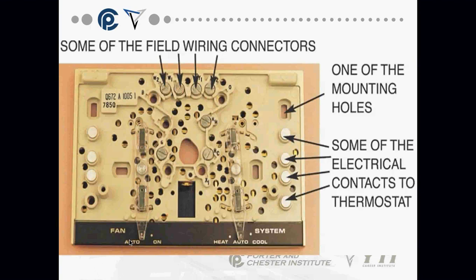So a thermostat subbase looks something like this, okay? We have spots for wiring connections up near the top. There's usually a spot where electrical contacts make contact with the thermostat that you're mounting above it. In the older style thermostats, we have our system switch and our fan switch, which we'll talk more about today, okay? We have our heat, auto, cool, or off. Okay, we have our auto and on fan switch. All of that is on the subbase. We have other wiring connections here as well. And if you look closely, you can see that they're all labeled like RH, RC. Okay, we have W, W, Y, and Y. Okay, so all of these wiring connections are labeled. And specific purpose of all these wiring connections.